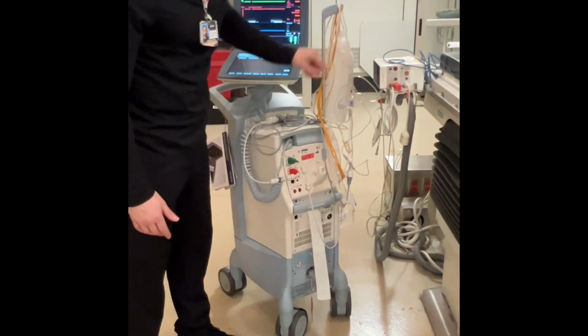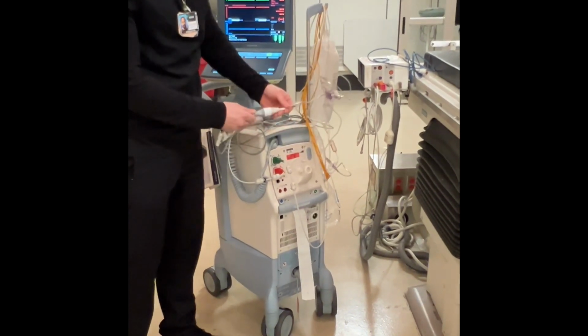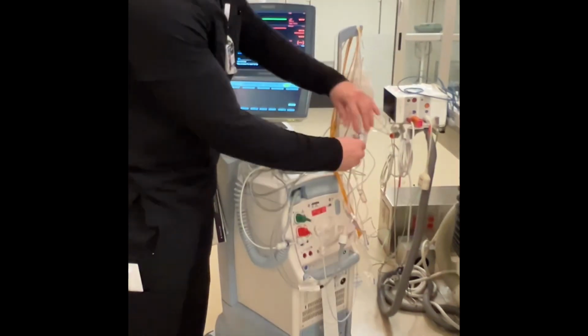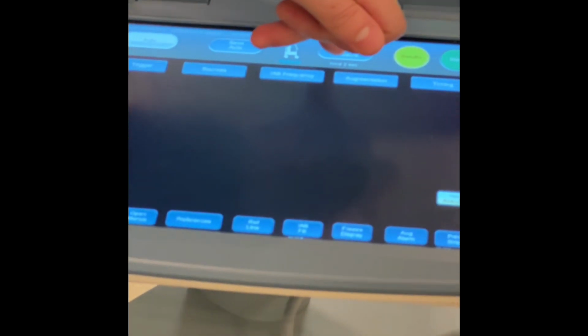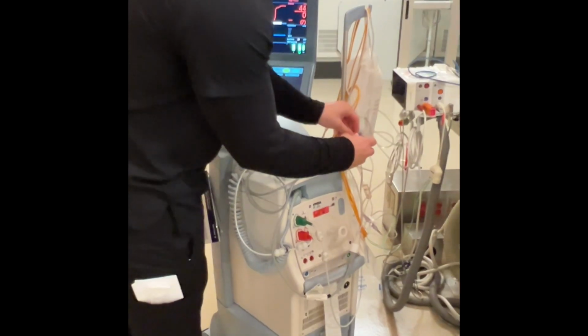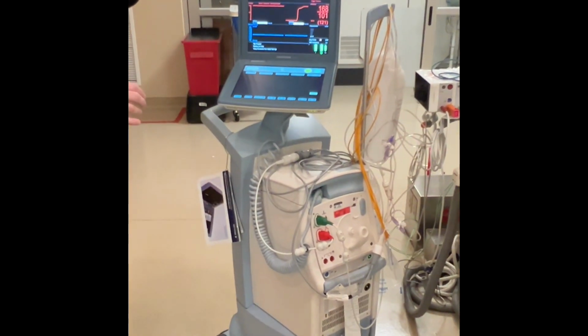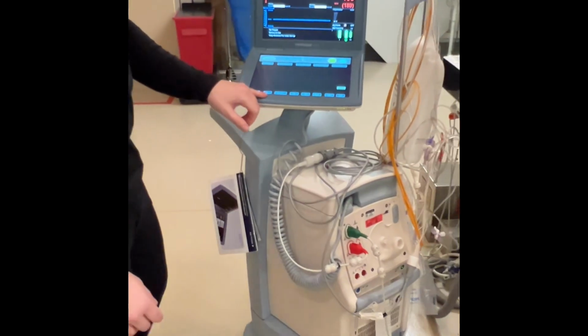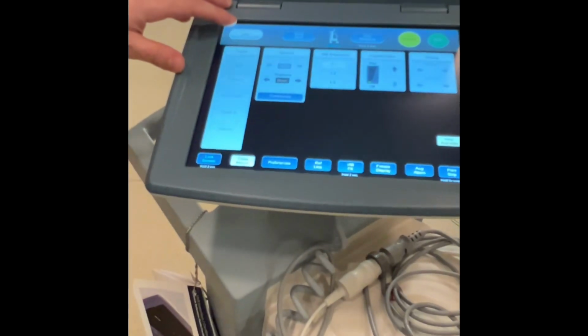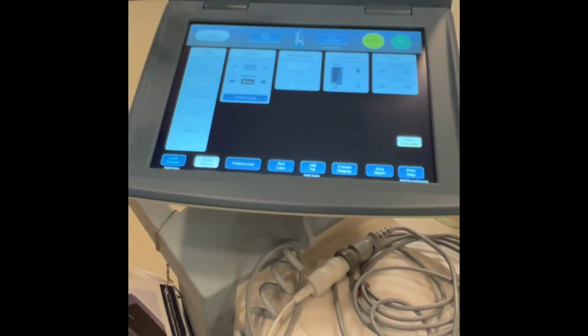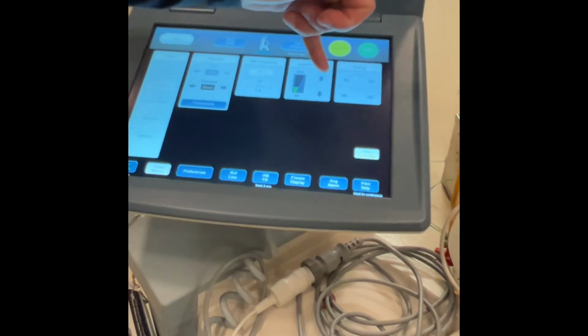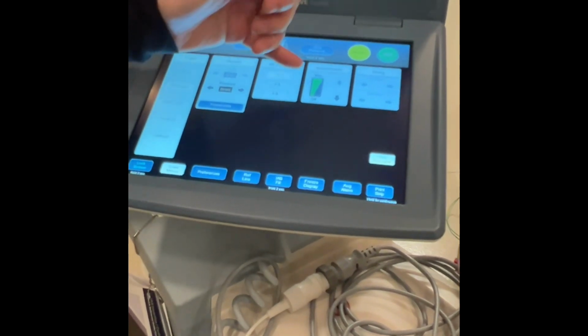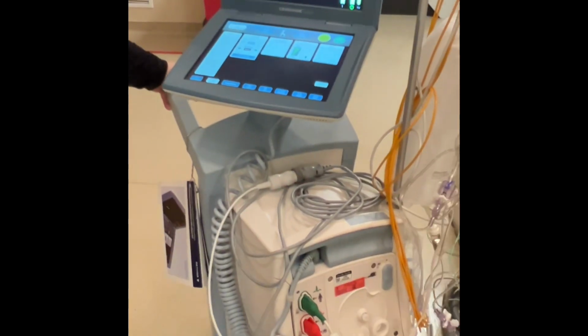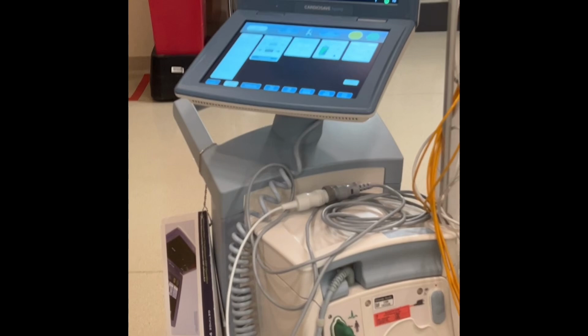Once you have this set up, you're going to go ahead and hook up your pressure line to your transducer. And then we're going to open it up, just like an A-line. And then we're going to hit 0 on the screen, hold for 2 seconds. Once we're 0, put this back. And then while we're waiting, we're going to check our settings. You're going to come down here to open menus. Make sure you're on auto, frequency 1 to 1. And we're going to have to turn our augmentation up to max. Whenever you turn the machine on, it always starts out at the lowest setting, so we have to turn that up. So now we're ready, and we're just waiting for the balloon.